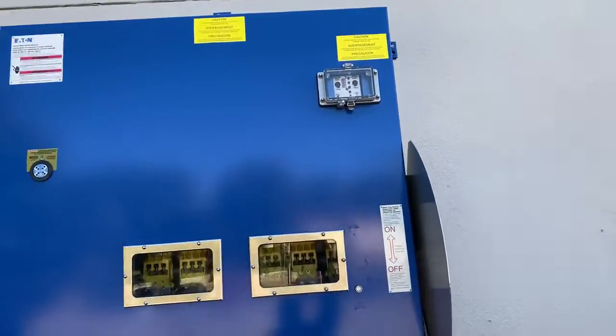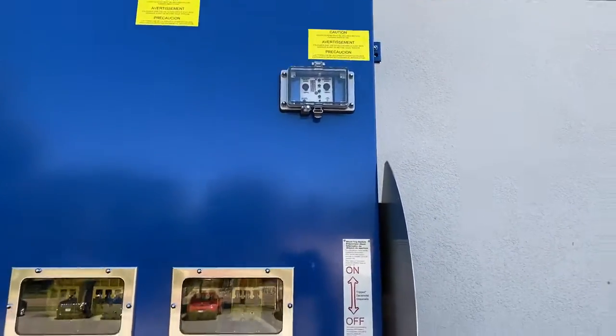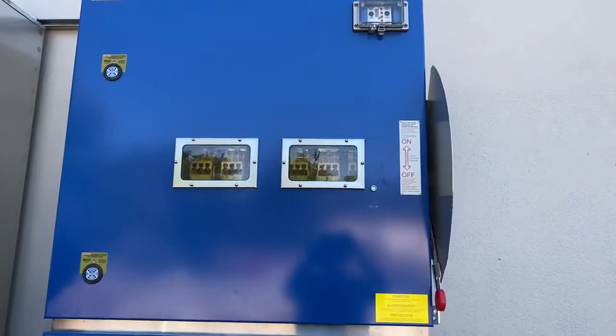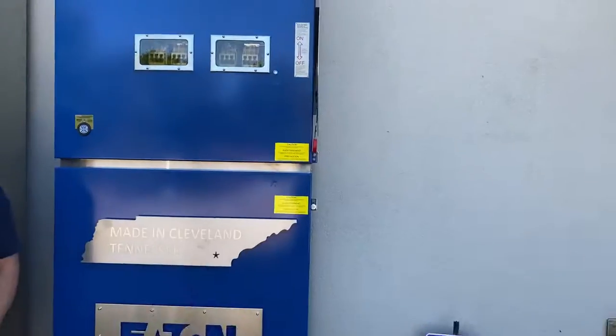And there's your ground fault protection of equipment. Yep, and what I love is that they put it through the door. So word of advice: relays like that, really great to request that, because I don't know that would be standard. I believe that's probably something they made for this equipment, but you would want access to those relays through the door—it helps the electrical worker from a safety perspective, they don't have to open that door. And this is a very big door.